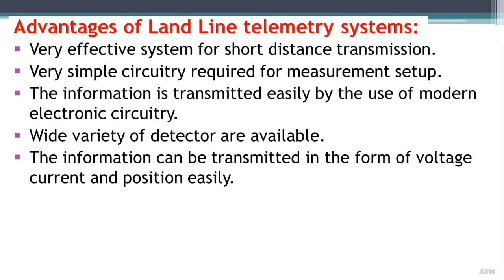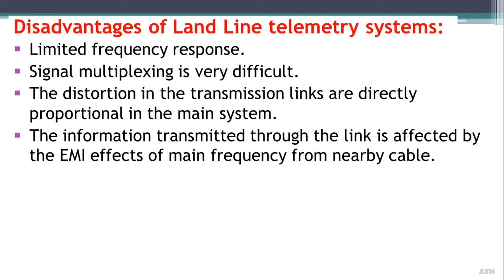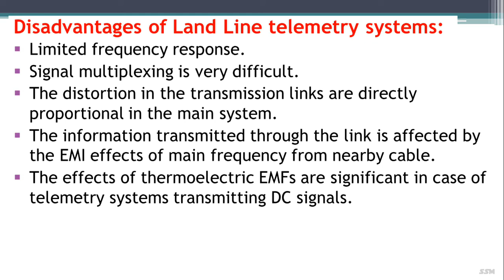The disadvantages of landline systems are limited frequency response, signal multiplexing is very difficult, the distortion in the transmission links is directly proportional to the main system, and the information transmitted through the link is affected by the EMI effects of mains frequency from nearby cables. The effects of thermoelectric EMFs are significant in the case of telemetry systems transmitting DC signals. These are the disadvantages of landline telemetry systems.